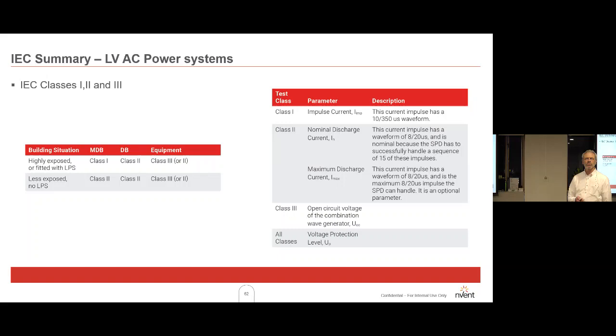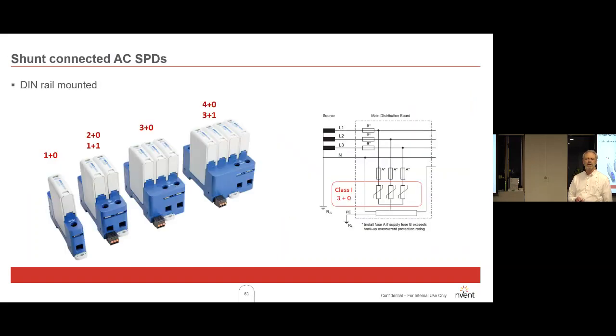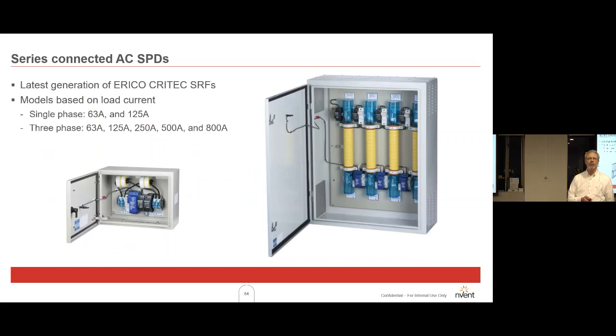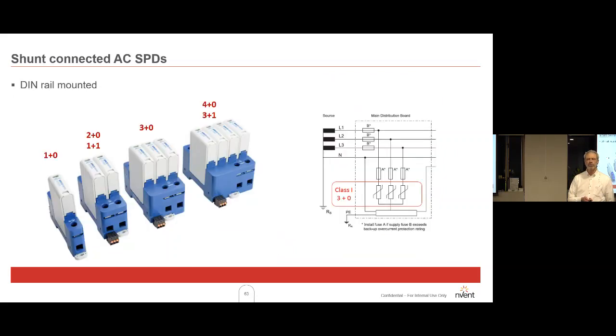That's just a table suggesting what you should put where, and that's an example of different surge diverters. This one here is a single phase one. For 3-phase systems at the main switchboard, the 3+0 example provides a surge diverter for each phase only, as explained on that earlier slide, and as shown here on the diagram on the right. The 4-module surge diverter can be used for distribution boards, where the 4th module goes between neutral and earth.